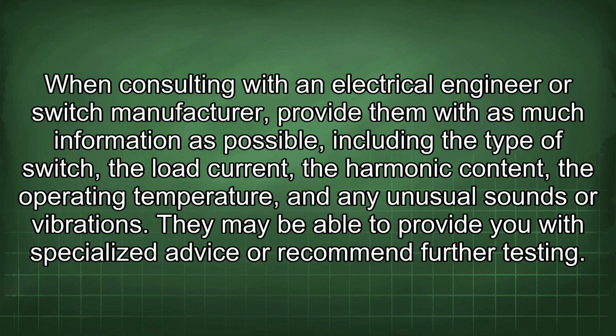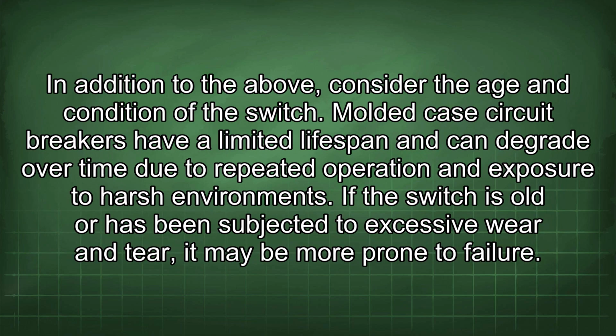When consulting with an electrical engineer or switch manufacturer, provide them with as much information as possible, including the type of switch, the load current, the harmonic content, the operating temperature, and any unusual sounds or vibrations. They may be able to provide you with specialized advice or recommend further testing. In addition to the above, consider the age and condition of the switch. Molded case circuit breakers have a limited lifespan and can degrade over time due to repeated operation and exposure to harsh environments.